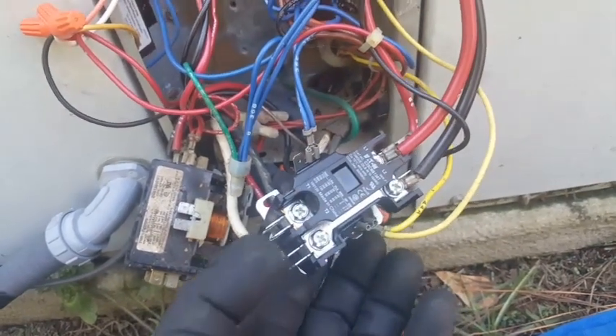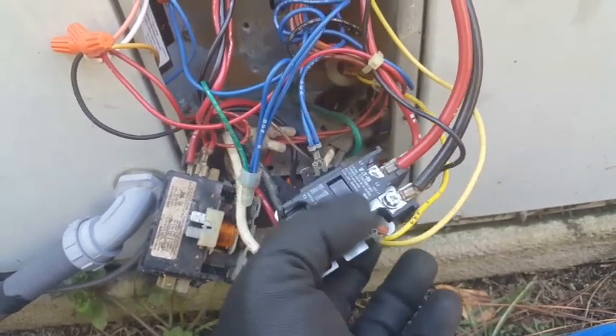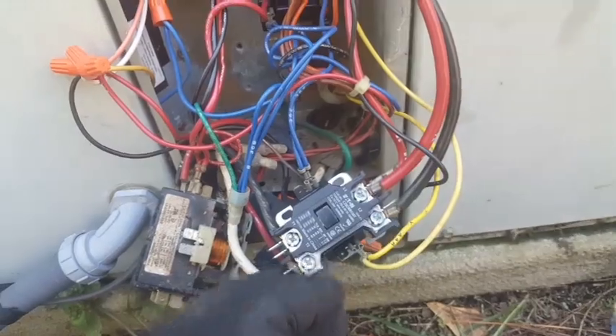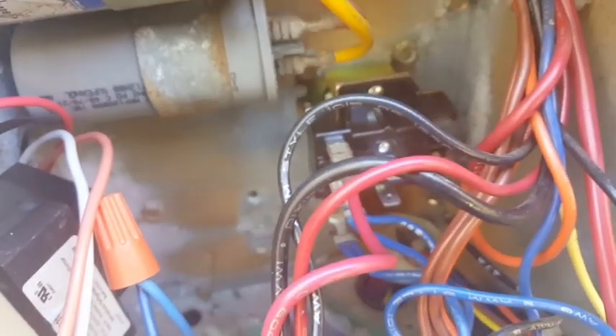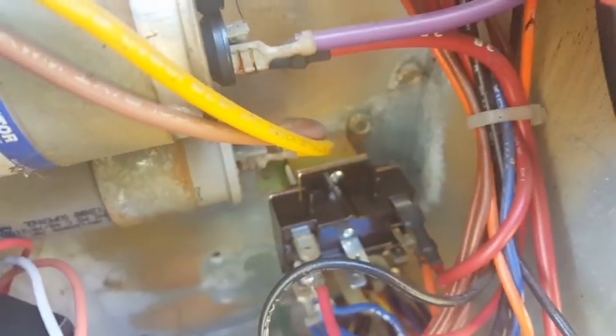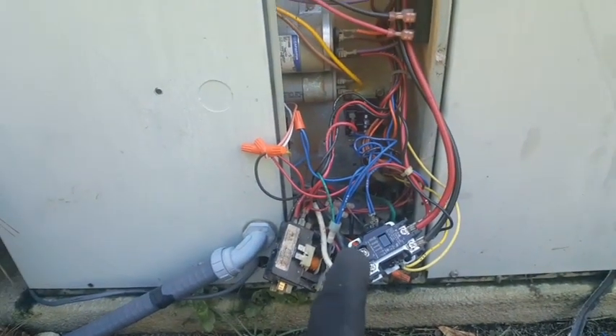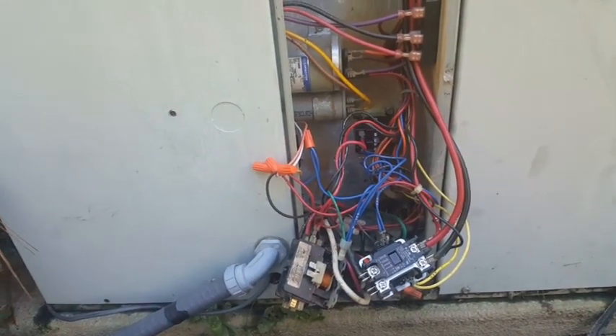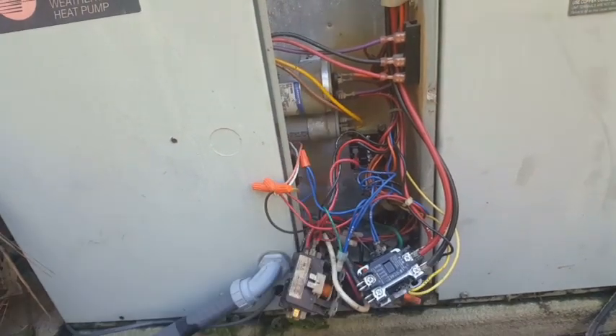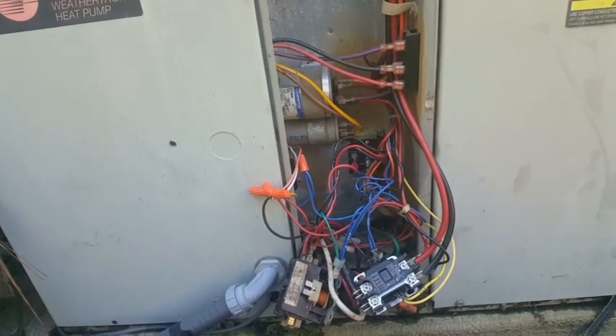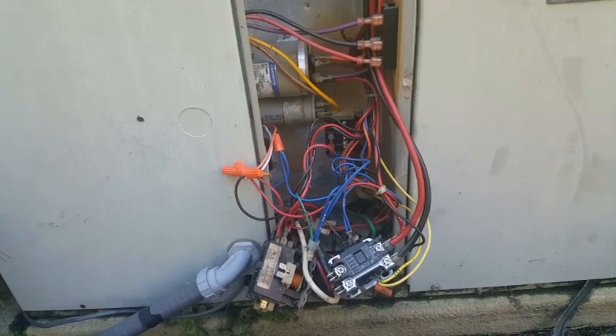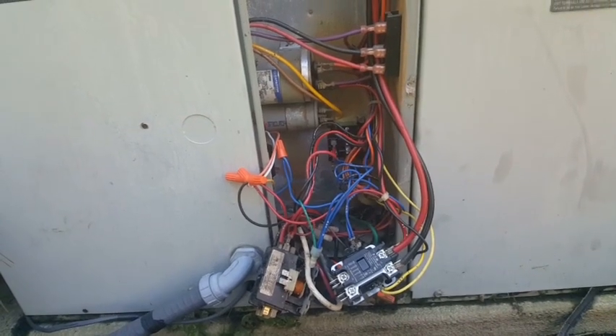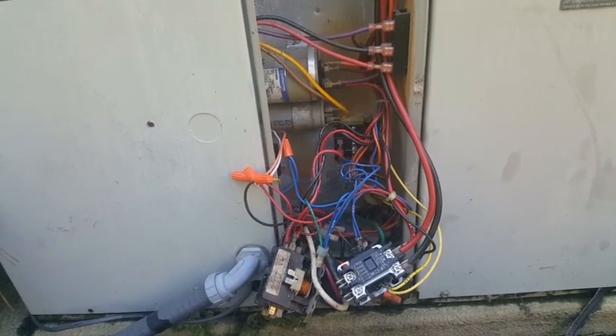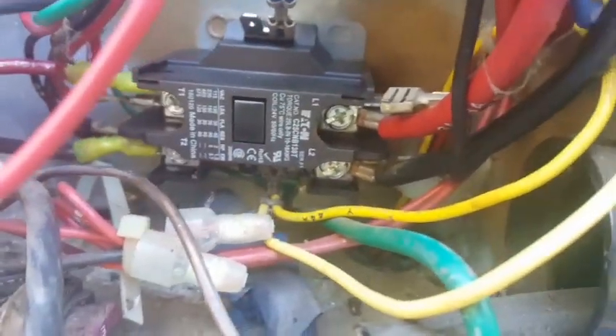The old contactor is coming out. Only thing left is the wiring on this side of the contactor leading in from the field wiring, and single pole contactor. We have our double pole, double throw in place back there. You can see it. So I'm going to finish that wiring and mount this contactor on the inside, and then we can change these two run caps out and go drain some ductwork, and we should be well on our way to starting up this piece of crap.